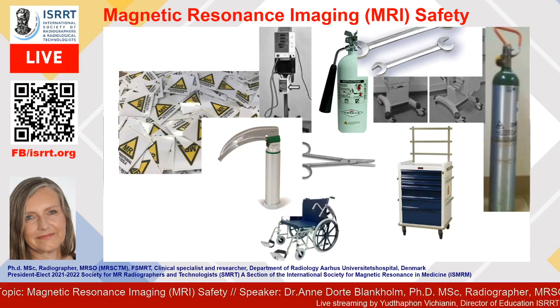And then we have the MR conditional labeling that for implants, with this labeling they can be scanned only on specific conditions, but also we can have equipment that are marked MR conditional. And when you look at this image, it's all equipment where there's a risk it might be brought into zone 4, and I encourage you to use these labels so that you mark everything where you think there's a risk that it may ever get close to an MR scanner.